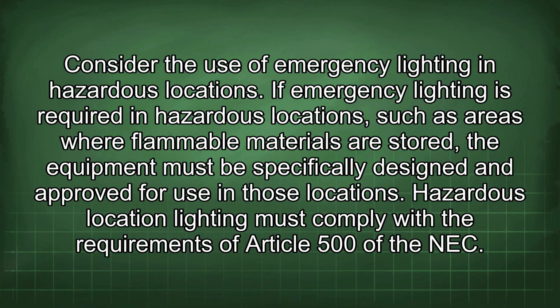Consider the use of emergency lighting in hazardous locations. If emergency lighting is required in hazardous locations, such as areas where flammable materials are stored, the equipment must be specifically designed and approved for use in those locations. Hazardous location lighting must comply with the requirements of Article 500 of the NEC.